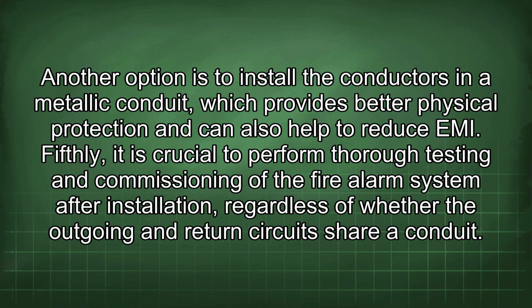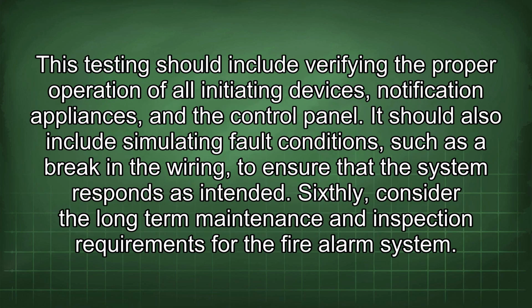Fifthly, it is crucial to perform thorough testing and commissioning of the fire alarm system after installation, regardless of whether the outgoing and return circuits share a conduit. This testing should include verifying the proper operation of all initiating devices, notification appliances, and the control panel.